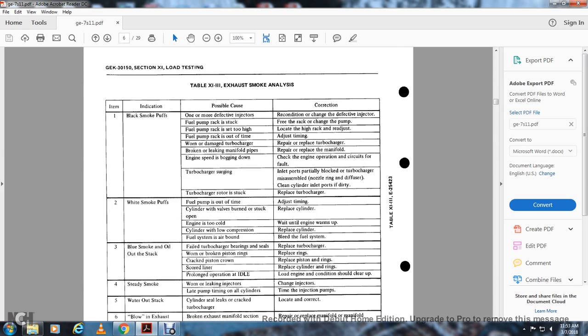Table 11.3, exhaust smoke analysis. 1. Black smoke puffs. Indication, possible causes: defective injectors. Correction: replace the defective injector. Fuel pump rack is stuck: free the rack and change the pump. Fuel rack is set too high: locate the high rack and readjust.